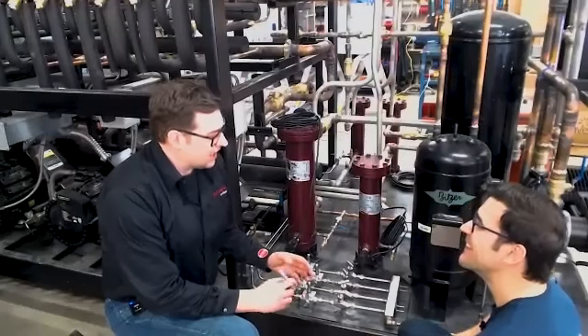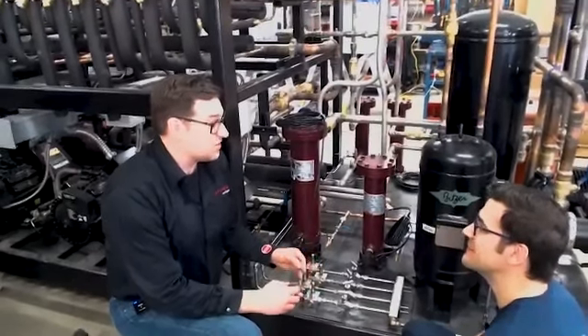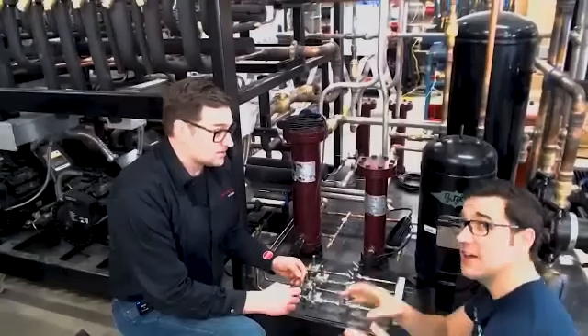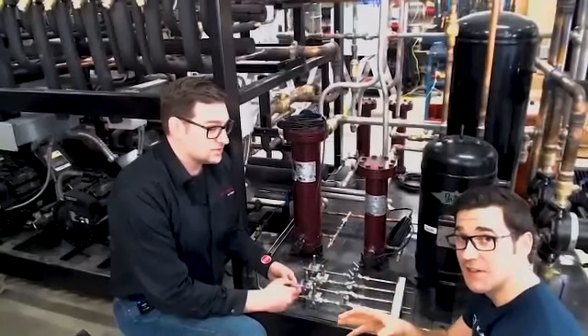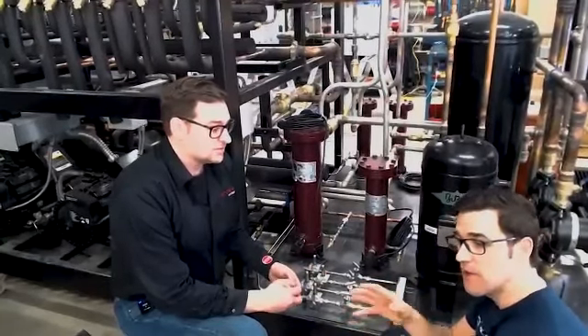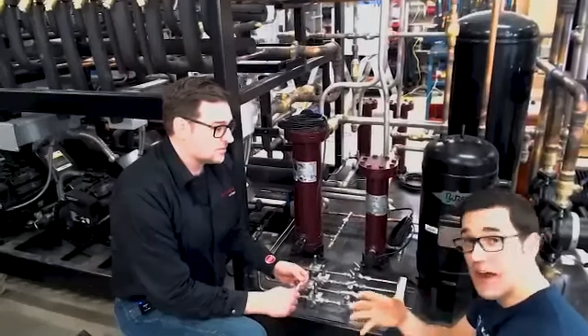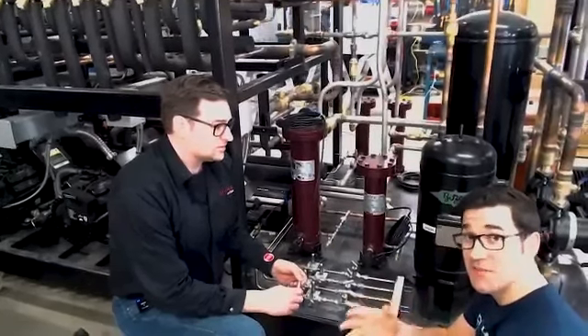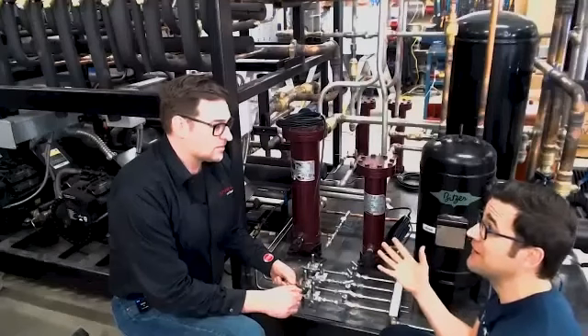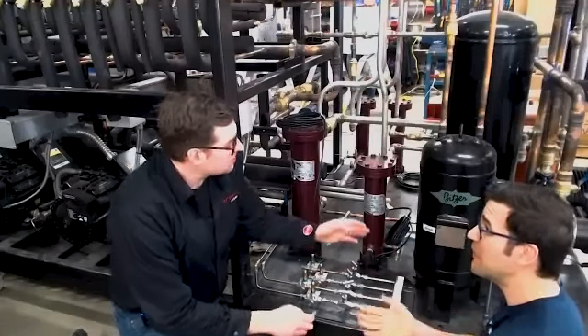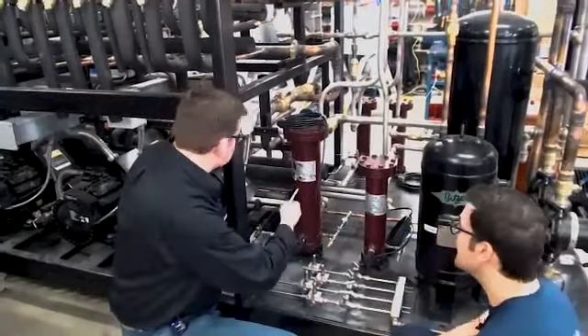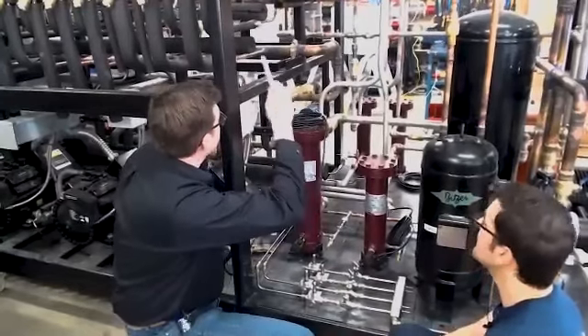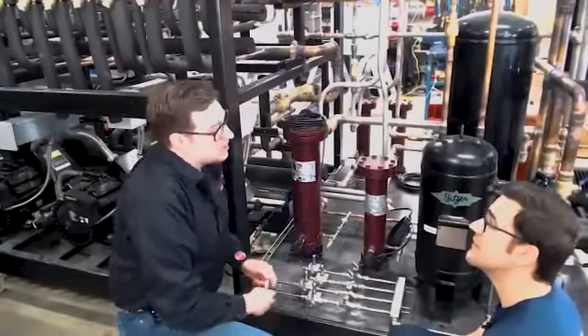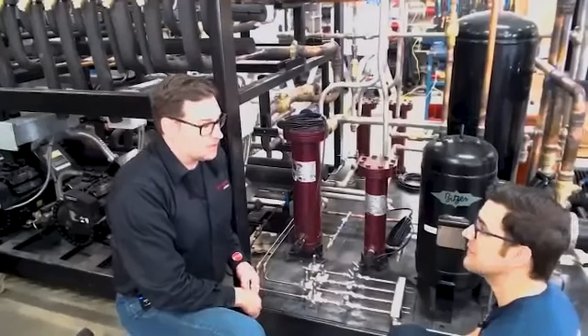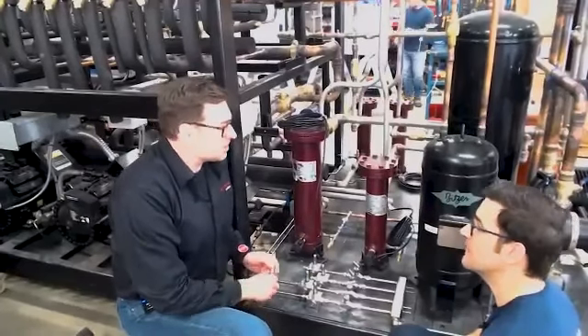We do HVAC applications where we have a differential of maybe 40. And did you hear that? HVAC applications - so CO2, if you're out there working in the HVAC world, commercial HVAC, you've got to start learning about CO2 because it's already here. But between the suction side here and our flash tank, we're going to have about 130 PSI differential to keep that moving.